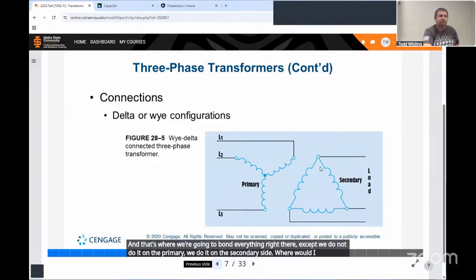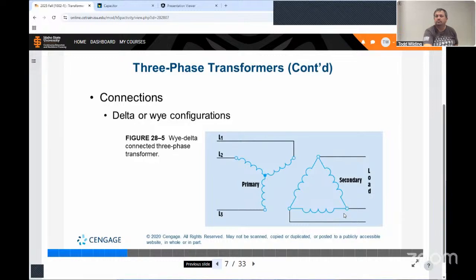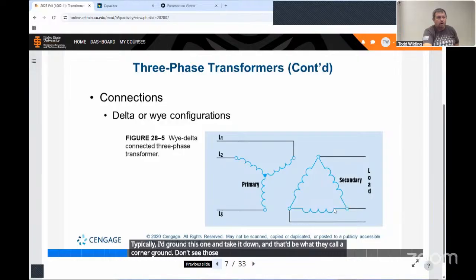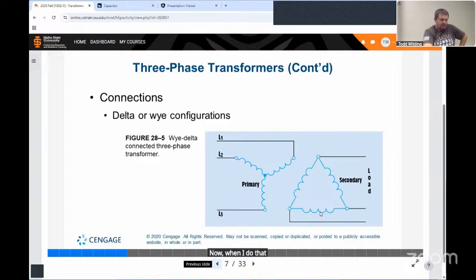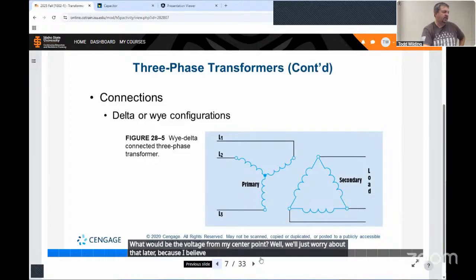Where would I derive my neutral in a delta connection? On a corner grounded system, it would be on a corner ground. Typically, I'd ground this one and take it down, and that'd be what they call a corner ground. Don't see those very often. More often than not, it's going to be in the center of one of the transformers. It'll be a center tap, and it'll come down and hit ground there. Now, when I do that, we'll probably talk about this a little bit later. When I do that, what would be the voltage from my center point? Well, we'll just worry about that later because I believe it will talk about it. Don't want to get ahead of the game here.